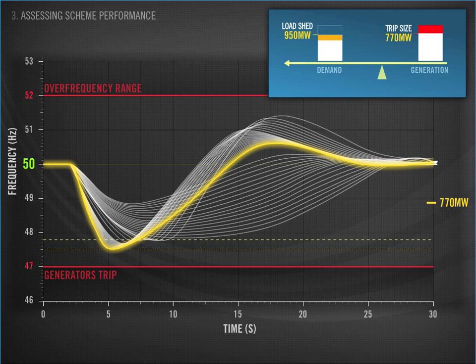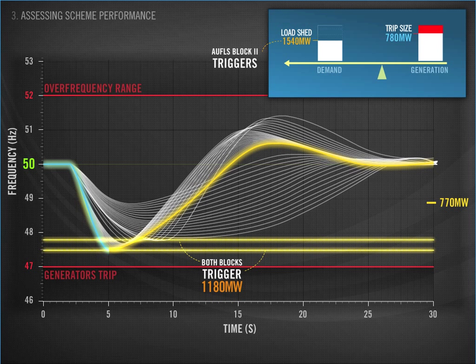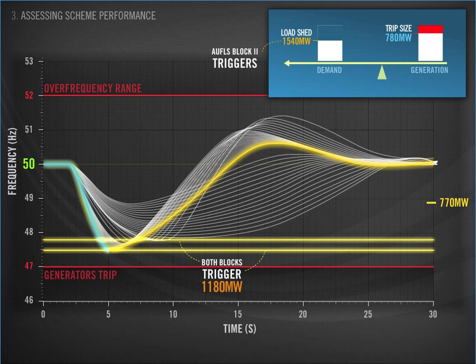In the simulation, 770 MW was the last size event that triggered only Block 1. An increase in trip size of only 10 MW of generation triggers UFLS Block 2. From that 10 MW increase in trip size, we have an additional 590 MW of load being shed, bringing the total load shed to 1,540 MW. You can probably imagine what is going to happen as a result.